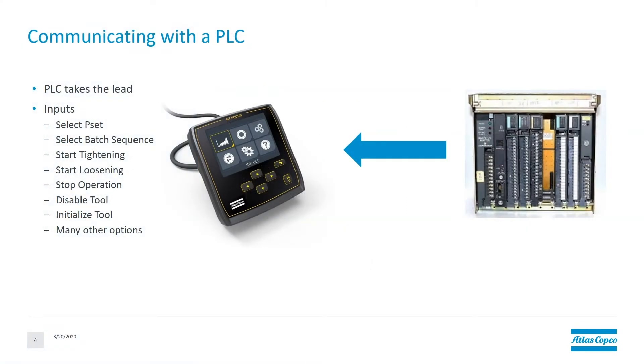Let's take an example of the MTF-6000 communicating with a PLC. In this situation, the PLC would take the lead. It could provide inputs to the MTF-6000. These inputs could tell the MTF-6000 to select a P-set, select a batch sequence, start the tightening, start loosening, stop what it's doing, disable the tool, initialize the tool, and there are many other options.